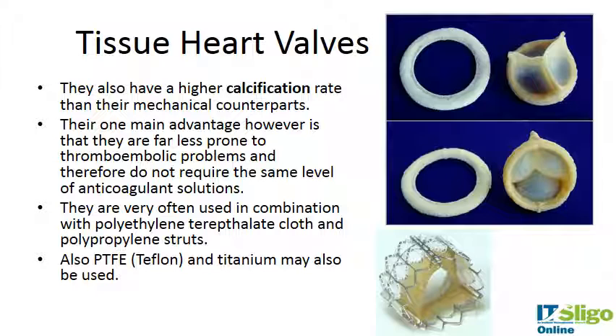Tissue valves also have higher calcification rates, where calcium deposits build on the valve, causing stenosis — blocking the valve from opening — and may cause blood regurgitation, clotting, and failure. The main advantage is they are far less prone to thromboembolic problems and don't require the same level of anticoagulant medication, making them more favorable for some patients. They are used in combination with polyethylene terephthalate cloth or polypropylene struts.